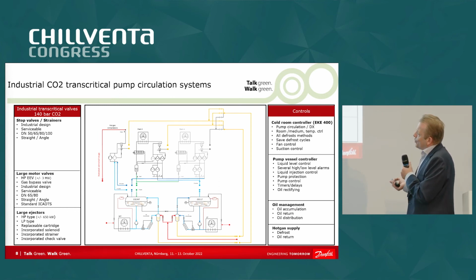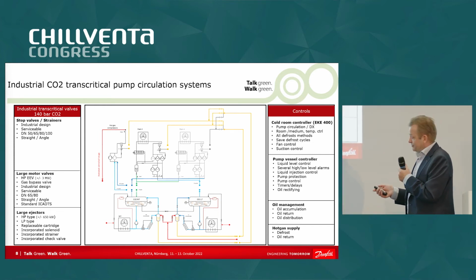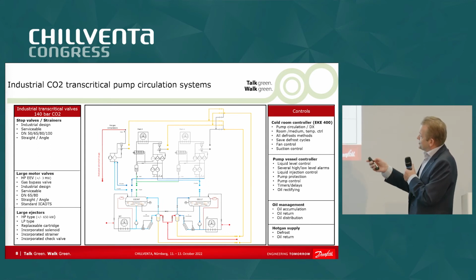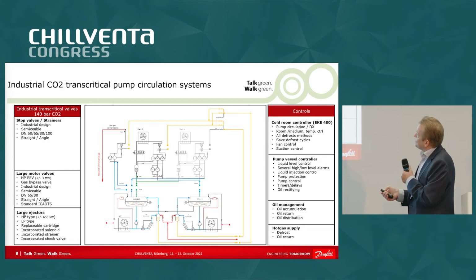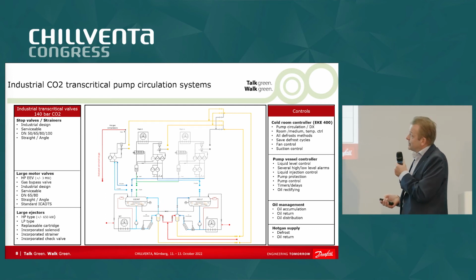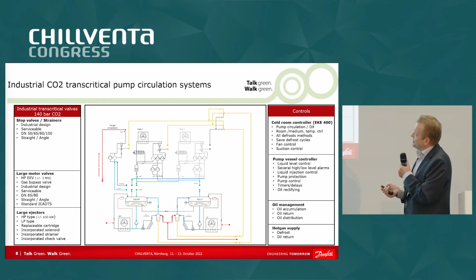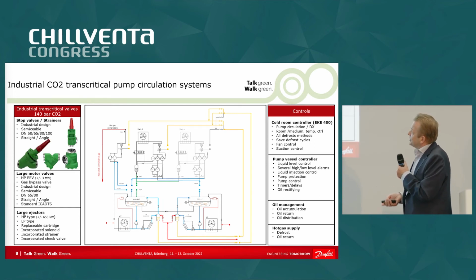So what should we do to make sure that these larger systems can be built? Well, we are working on quite some solutions. So this is the overall system again. We have a rack, transcritical rack. We could have another one if you like. The compressors become really big. So with one rack, you could probably do 1, 2, 3 megawatt, relatively simple. The problem is if this is going to be bigger, everything has to be big. So components have to be bigger. So that's the first thing that we have to look into. And that's what we did.